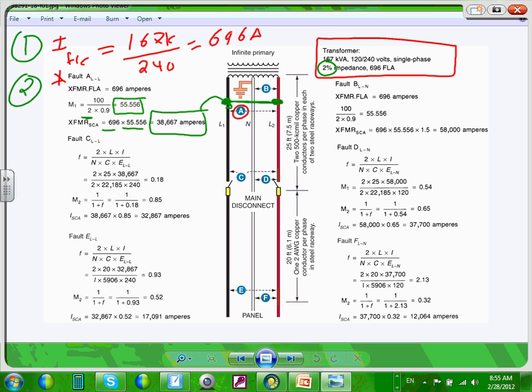Any question, guys, about finding the short circuit at the terminal of this single phase transformer? Up to this point, you guys have done it. We took the full load current divided by the impedance. That's exactly what they did. The only new stuff here is that they multiplied it by 0.9, because the impedance right here is plus or minus 10%.